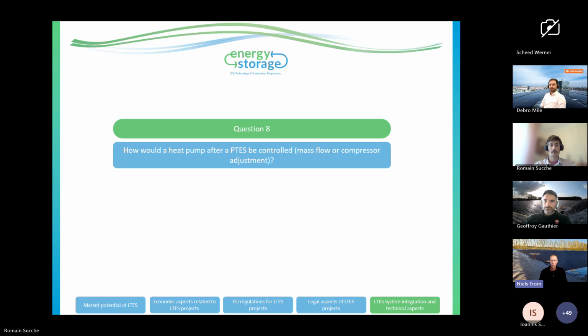If that should be improved, you should have a TTES in between the heat pump operation and the heat demand. But in case the water flow is controlled by the heat pump, I would say that the flow should be controlled by the condensing pressure, because then you have a short regulation circle in the system.